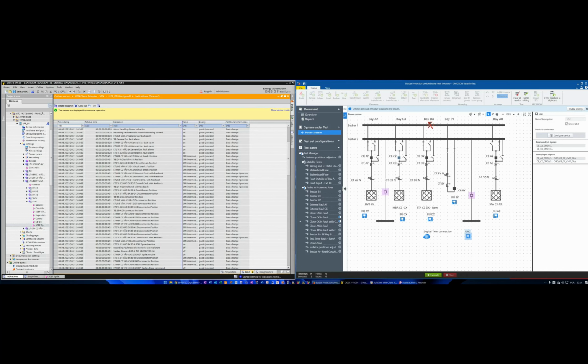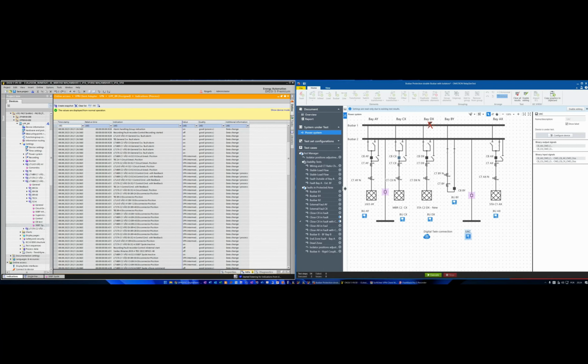For example, your contact will be stopped here. So here we see the circuit breaker was closed, and here the circuit breaker opens, but you have a flowing current here. So you can operate incorrectly in this case too.